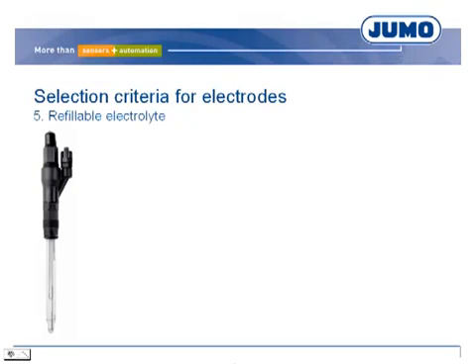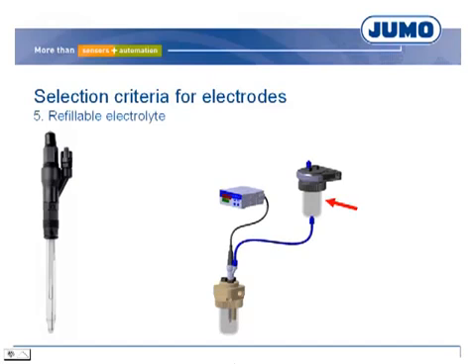In refillable electrodes there is a slight overpressure in the reference electrolyte, caused by the higher position of the storage vessel and possibly by primary pressure admission. The electrodes have one or more ceramic diaphragms, and due to the overpressure, there is a continuous flow into the measurement medium. This principle is normally used in cases of diaphragm blockage due to oil, applications in ultra-pure water, or measurement in media which poison the electrolyte.